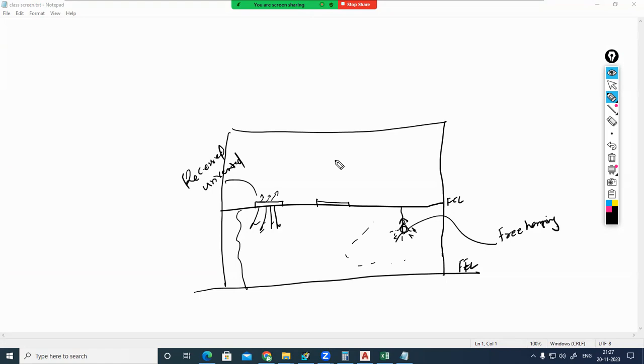But in recessed vented type light fitting, the light itself will be having small holes in it, small perforations, for ventilation. So a little amount of heat will be going upside, and at the same time air also will be going upside. Since it is having perforation in the light itself, the amount of air going above the false ceiling will be higher compared to the recessed unvented. The disadvantage is that when the return air is going upside, it will have contact with this air, and the return air temperature will be slightly increasing. But even in recessed unvented, the return air will heat up.